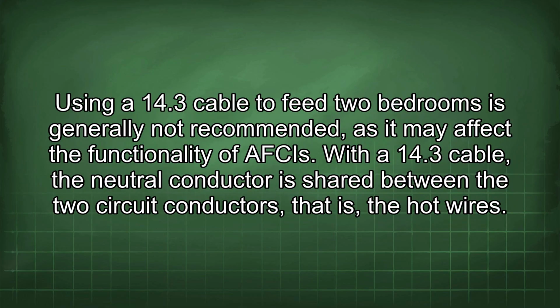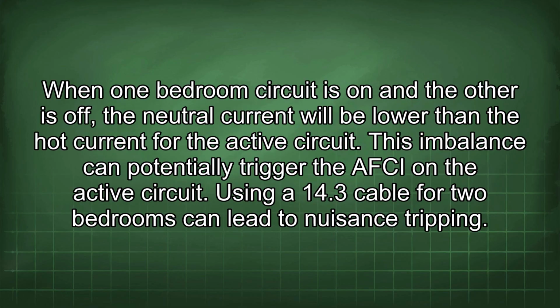Using a 14/3 cable to feed 2 bedrooms is generally not recommended, as it may affect the functionality of AFCIs. With the 14/3 cable, the neutral conductor is shared between the 2 circuit conductors, that is, the hot wires. When one bedroom circuit is on and the other is off, the neutral current will be lower than the hot current for the active circuit. This imbalance can potentially trigger the AFCI on the active circuit.